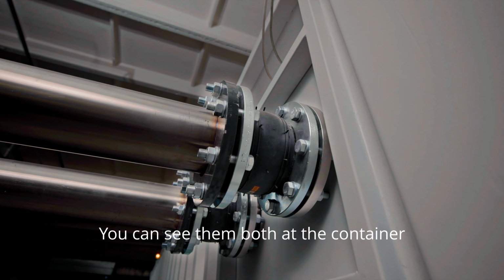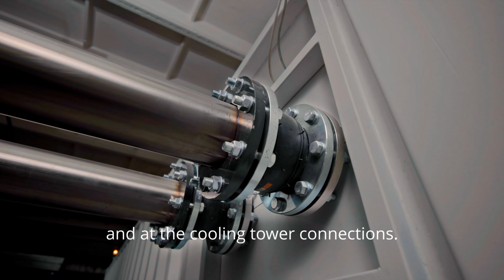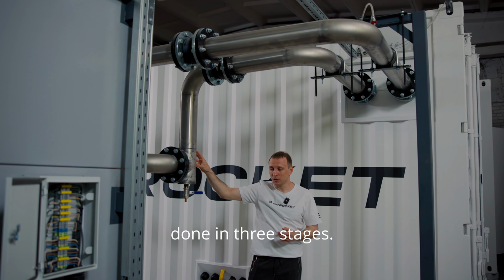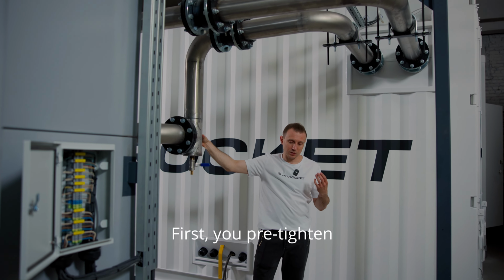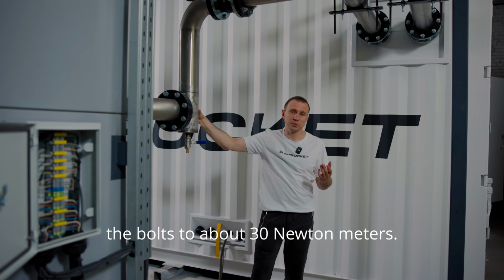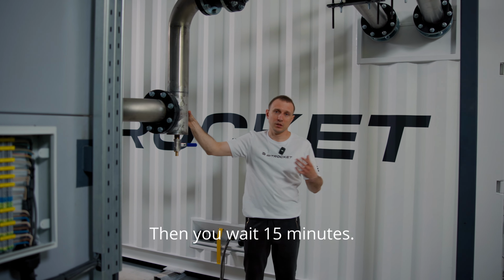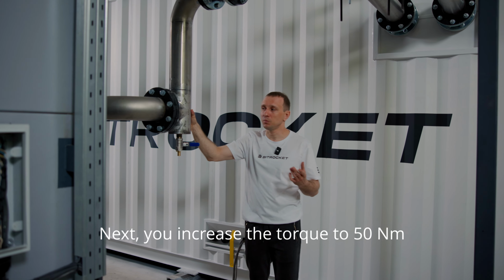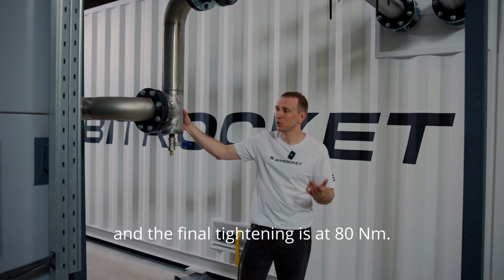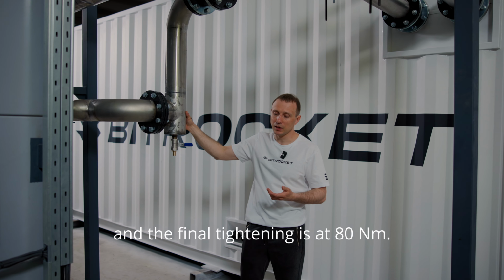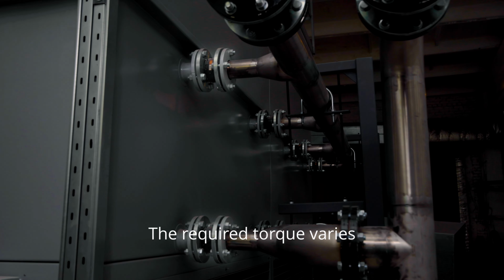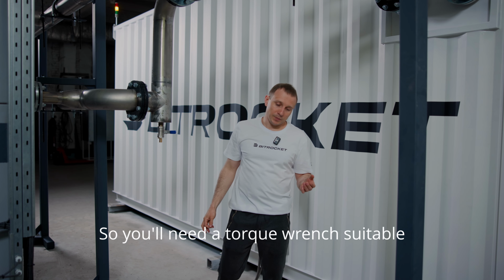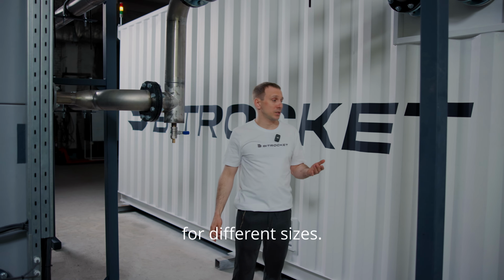You can see them both at the container and at the cooling tower connections. These connections are done in 3 stages. First, you pre-tighten the bolts to about 30 Newton meters. Then you wait 15 minutes. Next, you increase the torque to 50 Newton meters, and the final tightening is at 80 Newton meters. The required torque varies depending on the bolt diameter, so you'll need a torque wrench suitable for different sizes.